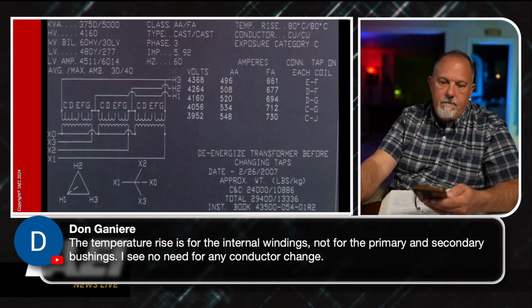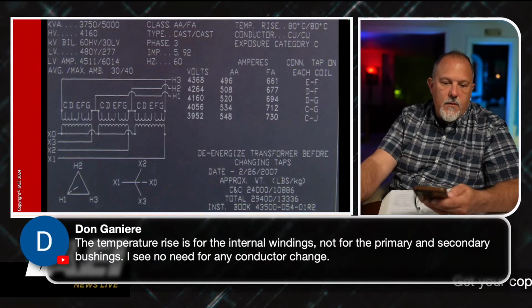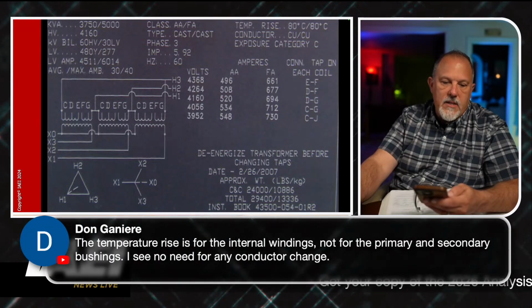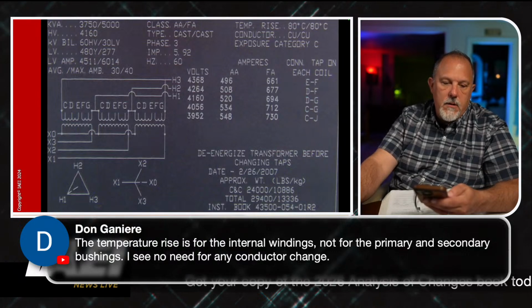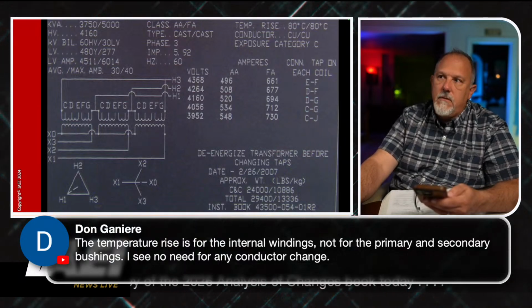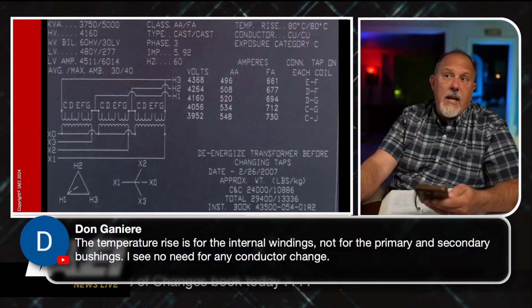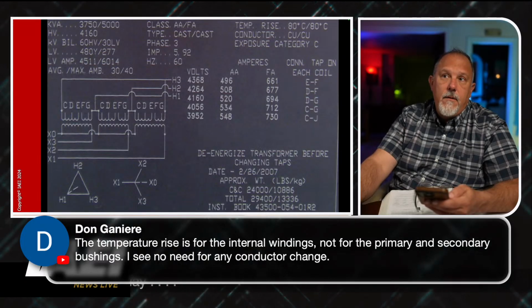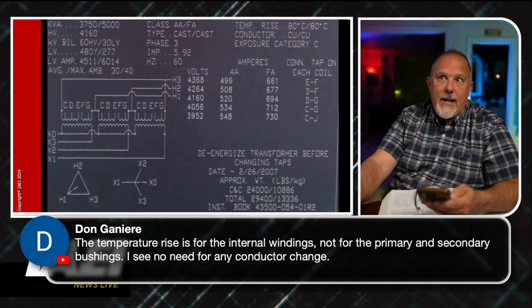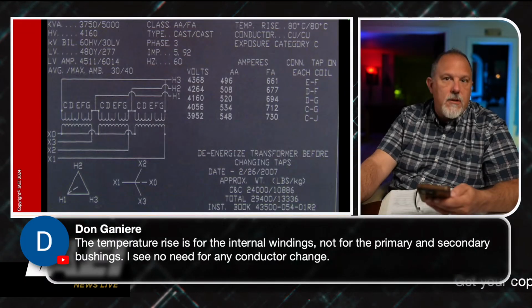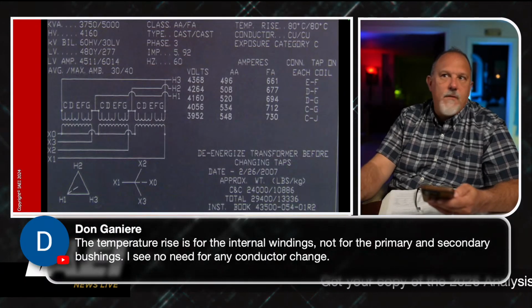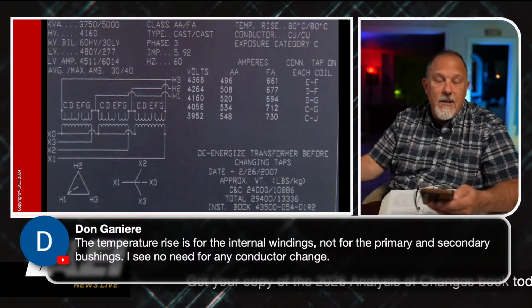You did. The temperature rise is for the internal windings, not for the primary and secondary bushings. I see no need for any conductor change. So you're saying that you would not see adding larger conductors on the secondary, because I have more full load amps, I can provide more current.